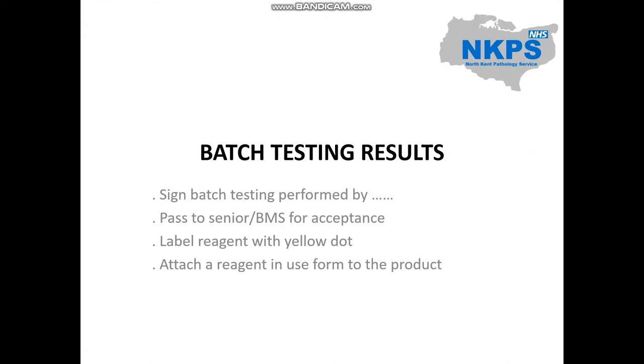Batch testing results. If the expected results are obtained, sign the batch testing 'performed by' section on the acceptance form and pass to a senior or BMS who has been signed off as competent in batch testing procedures. Once the BMS has signed it off as accepted, place the form in the relevant batch testing folder — there are two folders, one for Grifols and Bio-Rad cards and reagents, and one for all other reagents. Label the reagent with a yellow dot to show it has been batch tested and is ready for use. Attach a reagent in use form to the product, and if it has to be refrigerated, place it in the yellow bin in the cold room. Whoever puts the reagent into use should sign and date the reagent in use slip and place it in the Band 3 MLA tray for it to be updated in the batch testing folder accordingly.